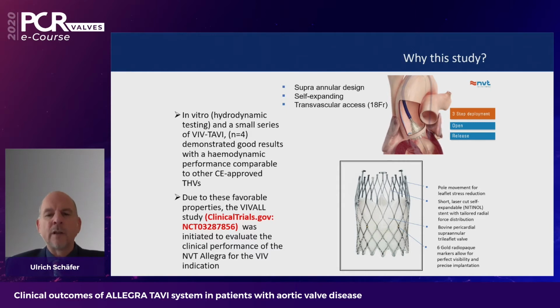The valve, as said, is a supra-annular valve design. It is self-expanding and is delivered via transvascular access through all commercially available 18-French sheaths. From in vitro testing and also a small clinical series, in the past we had good results pointing in the direction that the hemodynamics of this device are comparable to other CE-approved transcatheter heart valves. And due to these favorable properties of the ALLEGRA transcatheter heart valve, the VIVALL study was initiated to evaluate the clinical performance of this valve for the valve-in-valve indication.